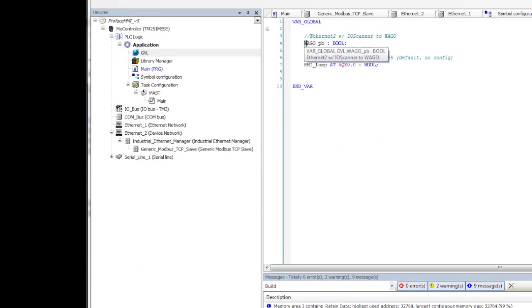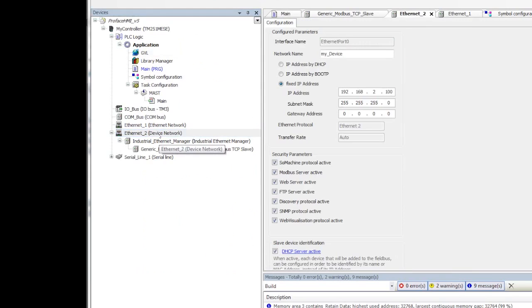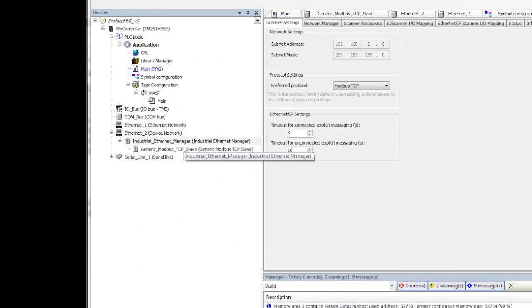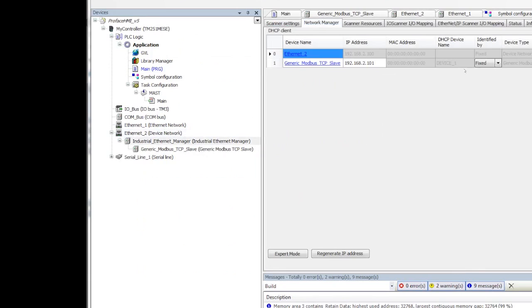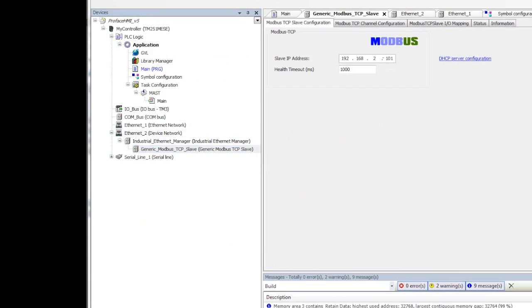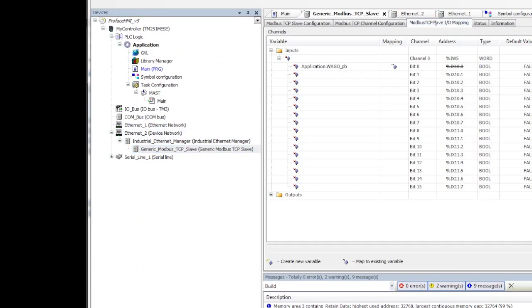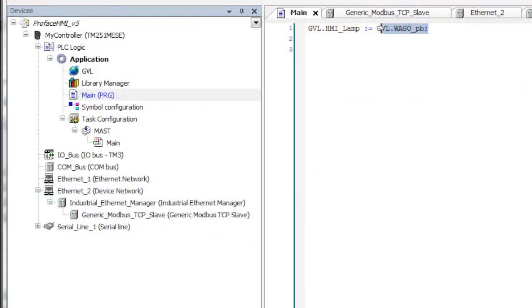So the WAGO_pb here is on the Ethernet 2, which is the I/O scanner. And you can see on Ethernet 2, I have it pointing to the WAGO. Actually, this is the PLC itself. And then in the Industrial Ethernet Manager, select Modbus TCP. And then I select fixed, and I point it to 101. And 101 is the WAGO island. Inside of here, I/O mapping. Here I have assigned the WAGO_pb to bit 0 as the input coming in. So the input comes in through the structured text program and gets written to the HMI. It's the HMI lamp.